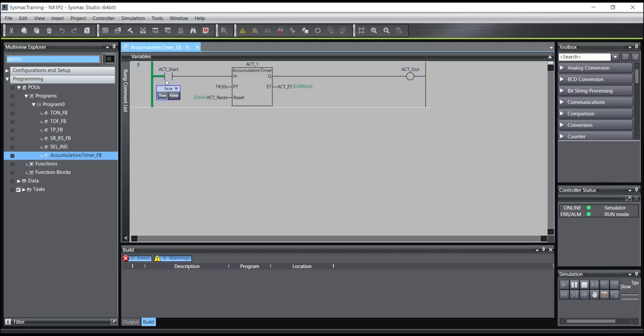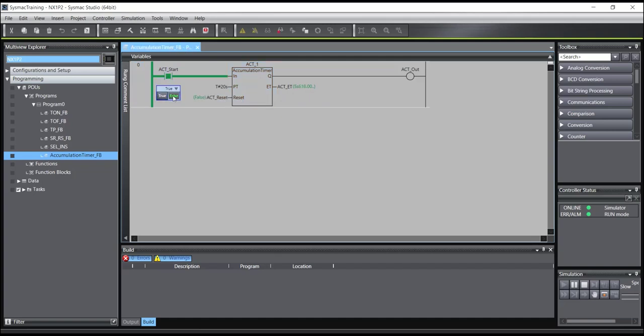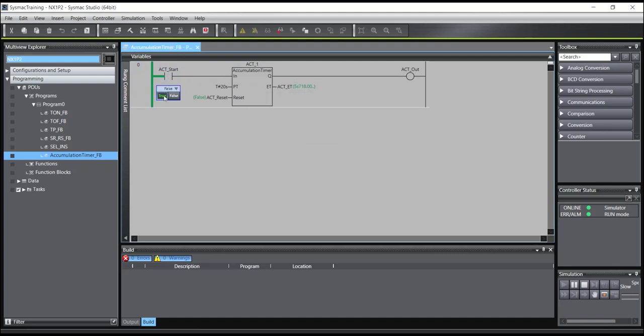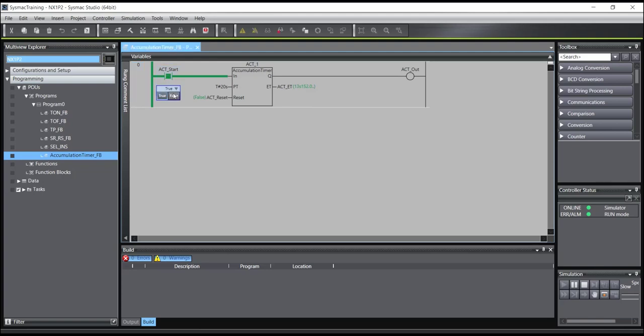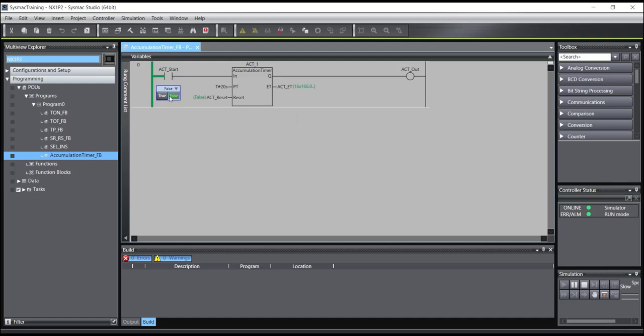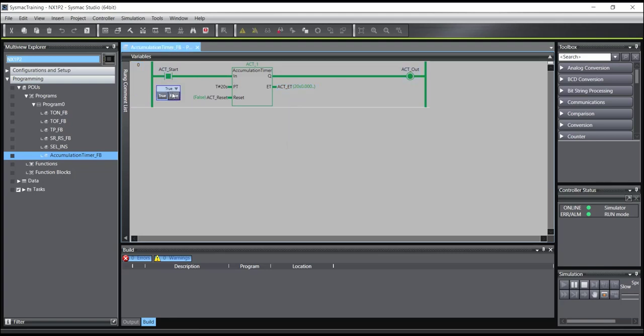Again I will test. I will start the counting for example 1 second, 2 seconds. Here I will turn off the input. You can see the time doesn't reset. And if I turn on the input, the timer takes time from the last number. And again I will turn off again. For example, now it's about 13 seconds. Turn on, it will continue. Turn off, and you see, when it reached 20 seconds, the output will be turned on.